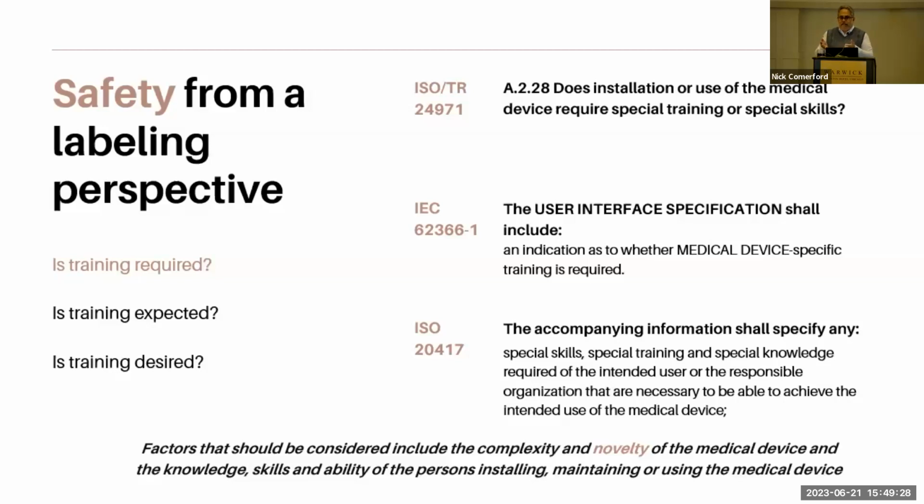Because you will have the need to generate training. It's good to have training. Customers like training, sales folks like training, but whether that training is a required training, that really is a differentiator. Required training versus training. Required training is the one that you have to fulfill all those regulatory requirements. General training, you don't. Aside from the stuff called out in 20417, that stuff you do.